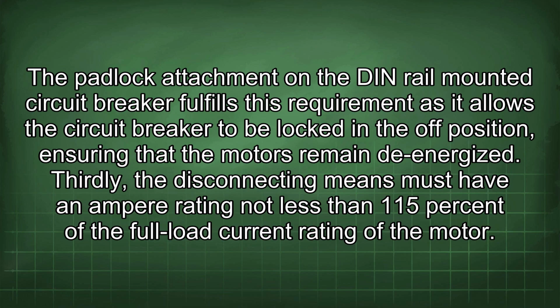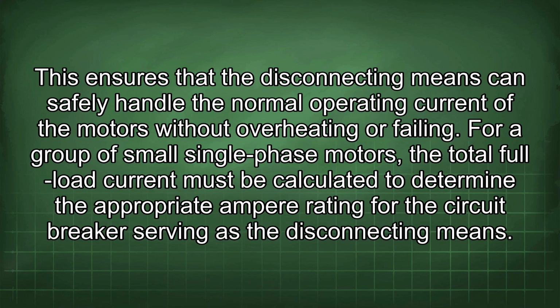Thirdly, the disconnecting means must have an ampere rating not less than 115% of the full load current rating of the motor. This ensures that the disconnecting means can safely handle the normal operating current of the motors without overheating or failing. For a group of small single-phase motors, the total full load current must be calculated to determine the appropriate ampere rating for the circuit breaker serving as the disconnecting means.